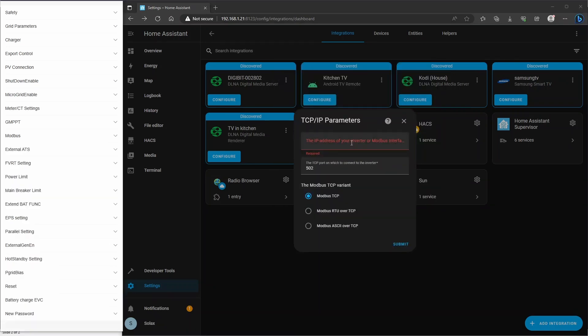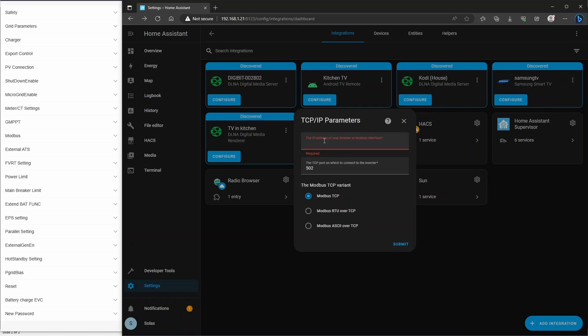Onto the next screen. Here you need the IP address of your inverter. So this is the IP address you set up when configuring the WiFi dongle. In my case, it's starting 192.168.1, and I set it to be a fixed IP address of 112. So you need to have recorded that. Remember I actually said to record them in a settings document to keep track of them. So put that in there now and leave the TCP port as 502 and the Modbus TCP selected there. And click Submit.